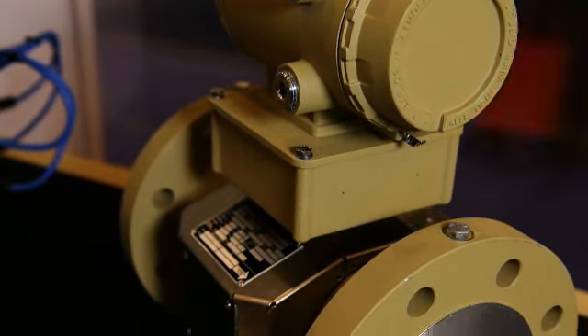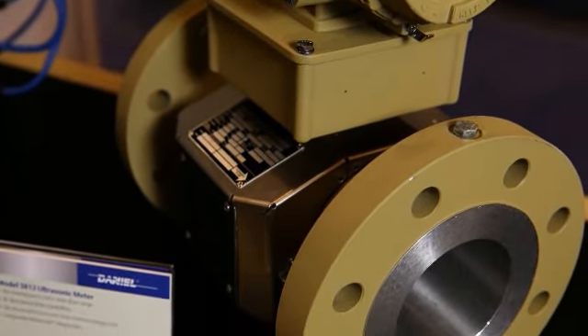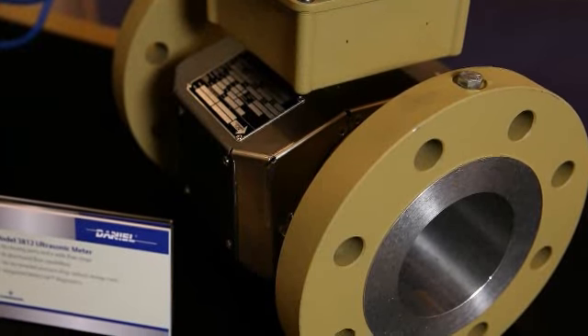The meter measures the flow rate of the liquid by firing pulses of sound with and against the flow. As a pulse of sound is fired with the flow, it tends to travel slightly faster than the speed of sound. As it's fired against the flow, it tends to travel slightly slower than the speed of sound. The difference between these two transit times is related to the flow rate of the liquid. So by measuring this flow rate on two separate paths, we can basically generate the average flow rate of the fluid flowing in the pipeline.